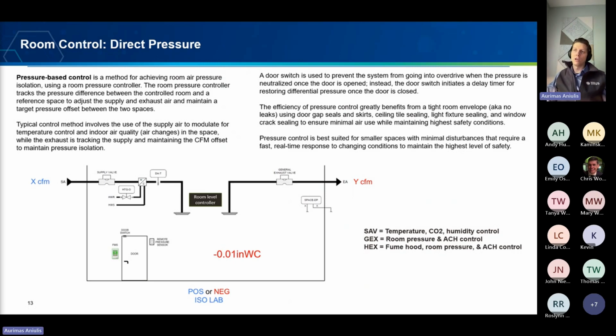In this example, we're showing that the target pressure differential between the control room and the reference hallway is 0.01, which is a typical set point that we see out in the field. In this case, this would be a negatively pressurized space, and we care less about the CFM. We still care about the CFM, but not as much, because as soon as my pressure set point is met, the CFM is going to throttle down to your air change set point and stay there to help you with efficiency.